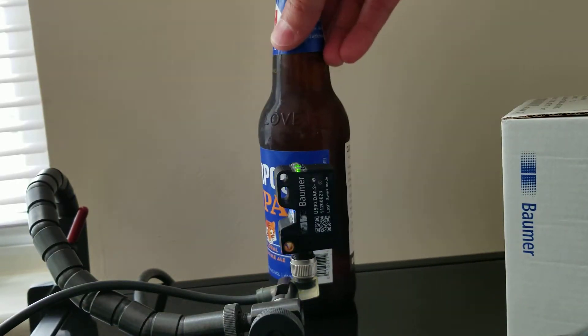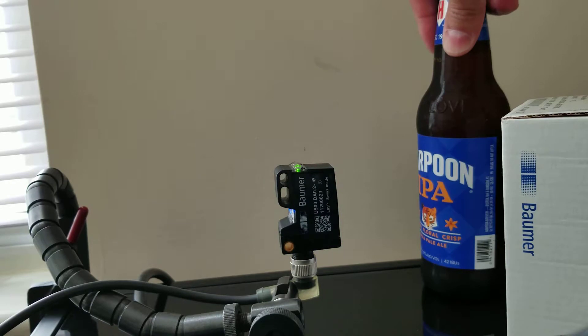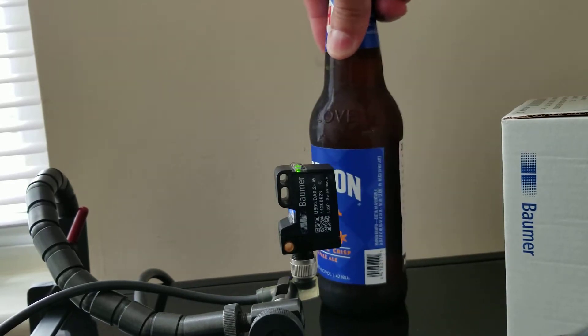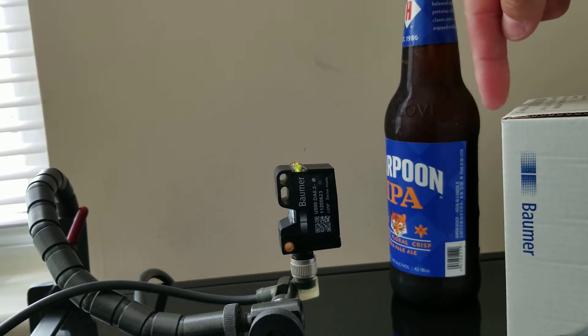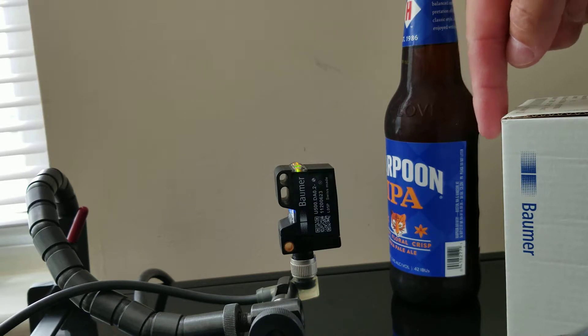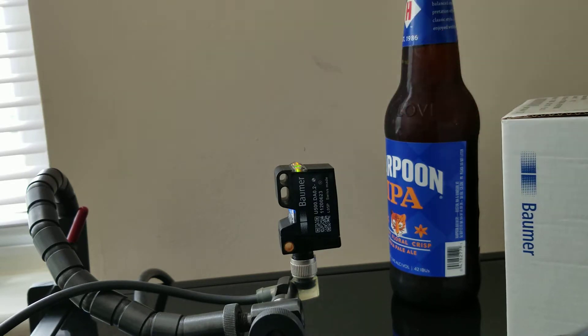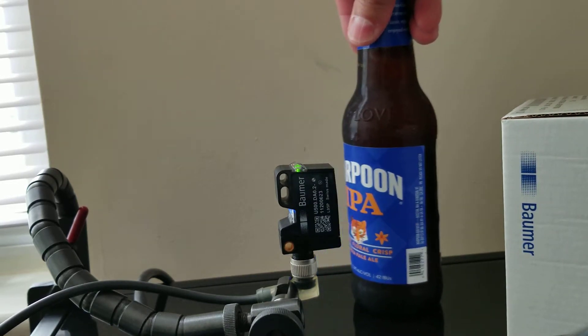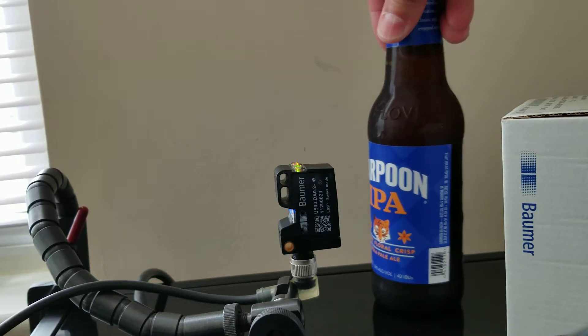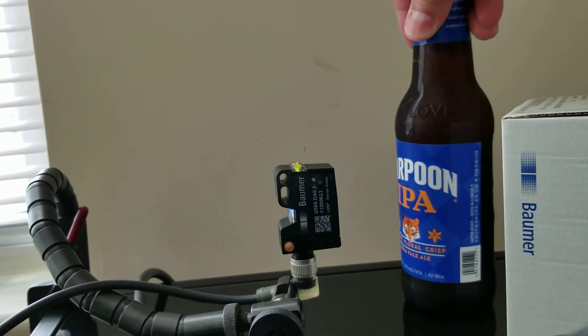And then when the bottle comes past, it'll trigger that sensor because the beam is actually coming off here, off this box which is at a 45-degree angle, hitting the bottle and then coming back to the sensor. So you see right there the sensor is going on and off as I go in front of it.